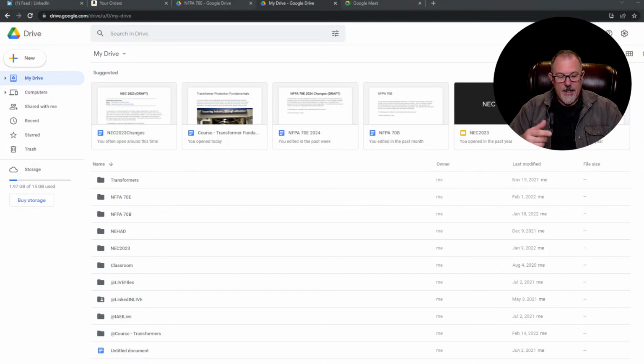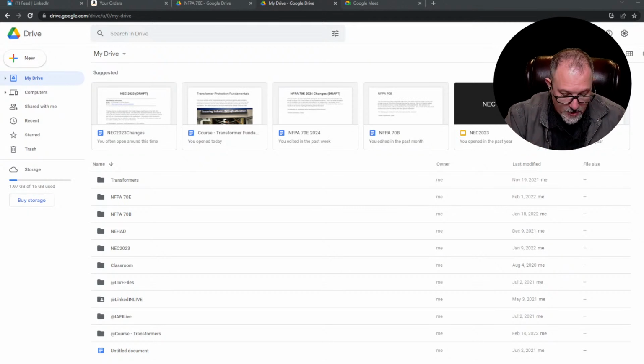You got to do a little bit of a leap, but modified - if you're putting in a different fuse, or changing the settings on a circuit breaker, you can't field adjust those settings to do whatever. You can't modify that, even on a temporary basis. How I came across 110.11 was there were people out there in arc reduction technologies telling contractors that all they need to do is turn the settings down on the breaker and turn them back up again. That's a violation of 110.11, or just willy-nilly doing it.